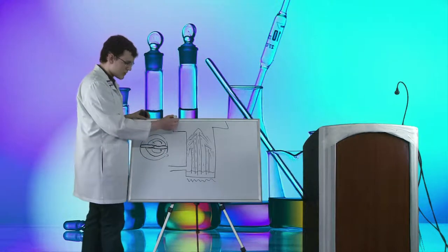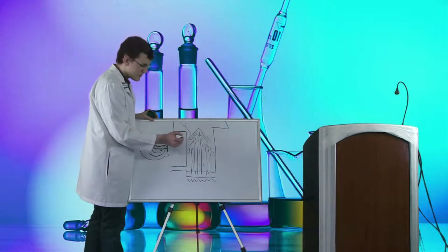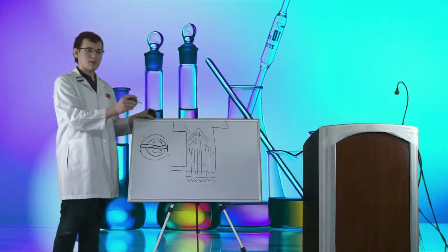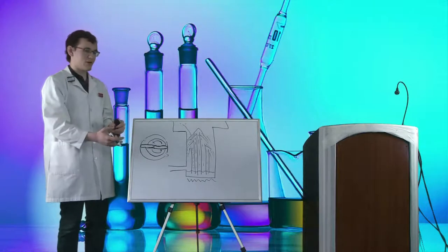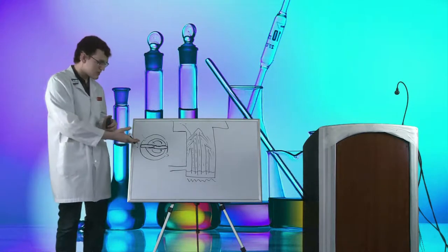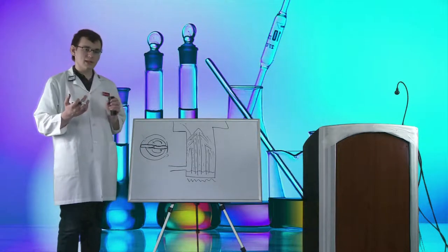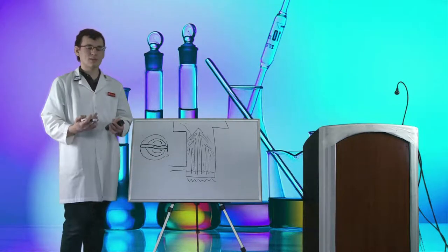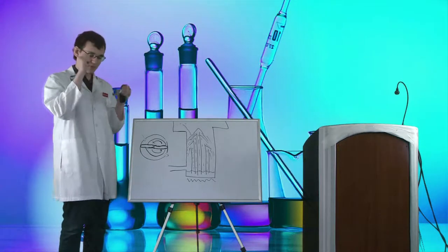When an air molecule comes by and flows into the pump, it physically gets hit by the oil vapor, and the oil vapor pushes the air molecules into the base of the pump. That's how boiling oil, directed in the right way, can pump a chamber down orders of magnitude more than a rotary pump can. That's what this class of molecular pump does — it physically hits the molecules of air with something to force them into the bottom of the pump.